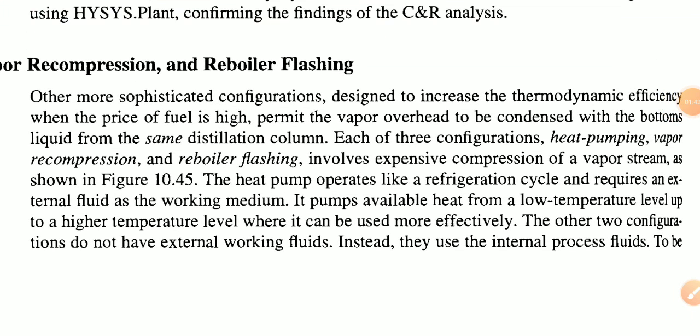Okay, now the other more sophisticated configurations, designed to increase the thermodynamic efficiency when the price of fuel is high, permit the overhead vapor to be condensed with the bottom liquid from the same distillation column. Each of the three configurations, heat pumping, vapor recompression and reboiler flashing, involves the expensive compression of a vapor stream, as in the figure.